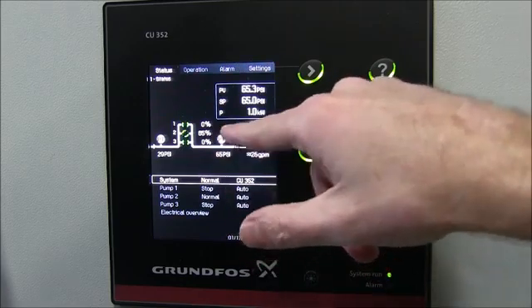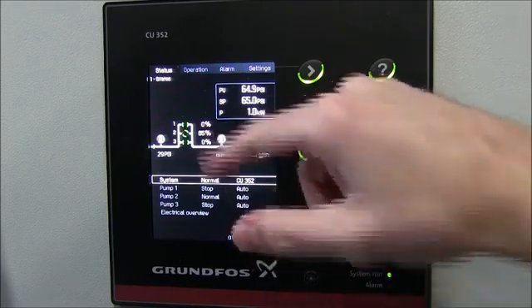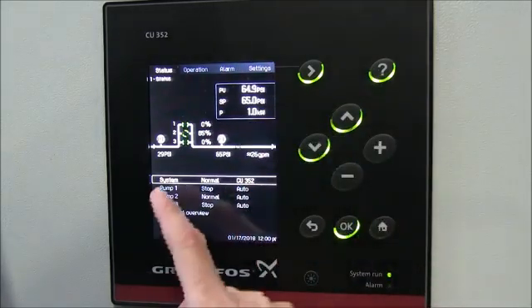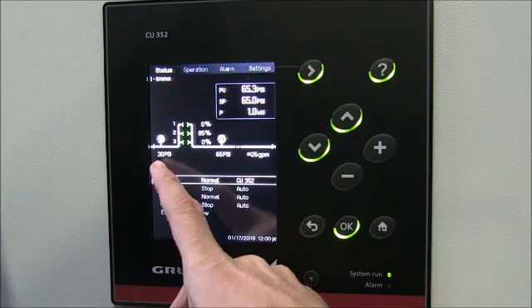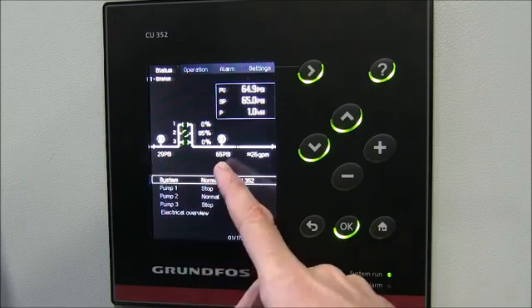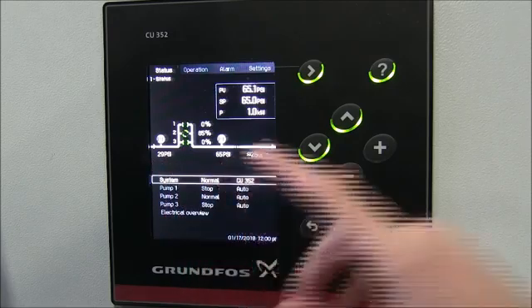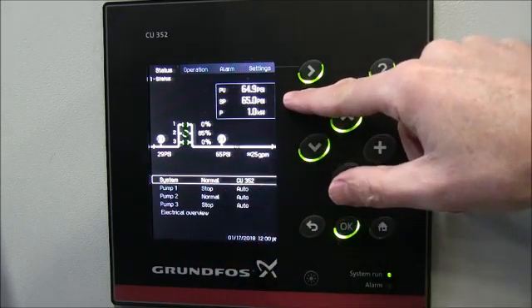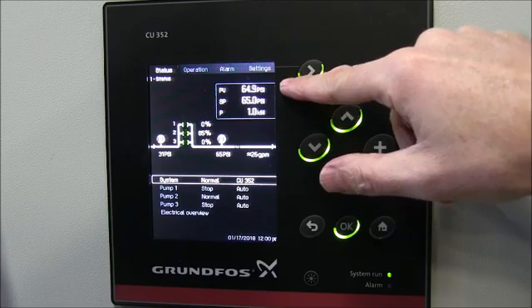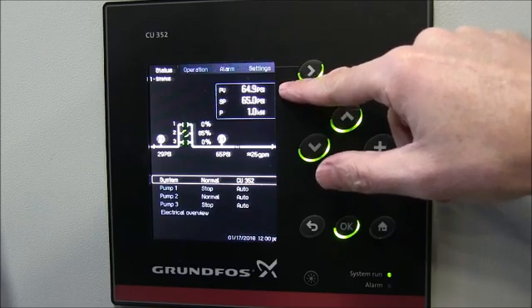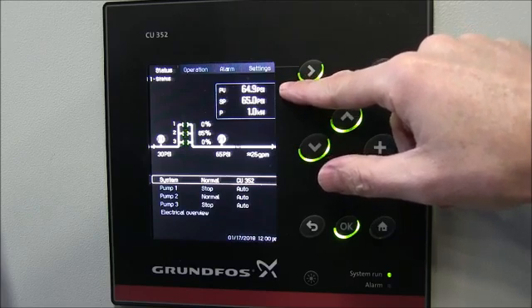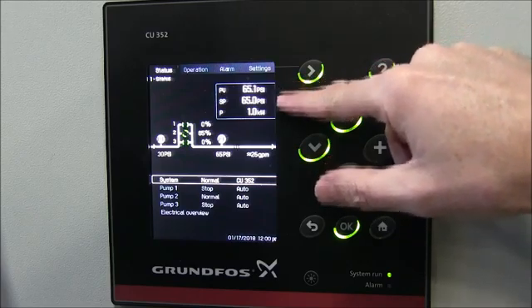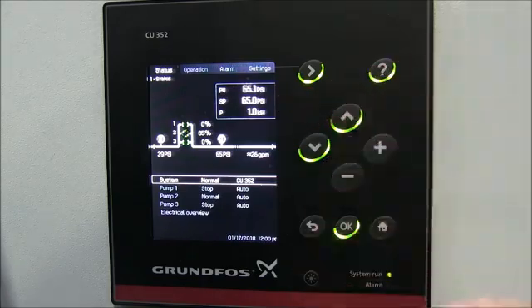We've got pump number two running at about 85 percent speed, suction pressure of about 29-30 psi, discharge pressure of 65 psi. 65 psi is our set point pressure and our PV — that's our sensor signal coming back, our process variable — so we're maintaining a 65 psi set point.